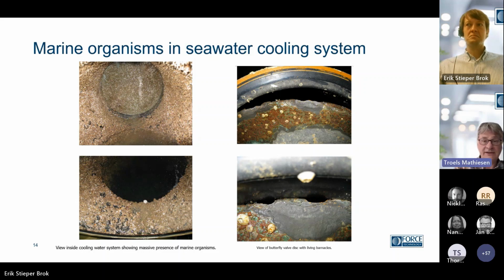One of the challenges for a cooling water system operating in seawater is marine organisms. They tend to settle on the internal surfaces, as you see here. We have barnacles covering almost the entire surface, and this will disturb the operation of the cooling water system - lower flow, lower heat transfer, perhaps plugging of filters, and so on.